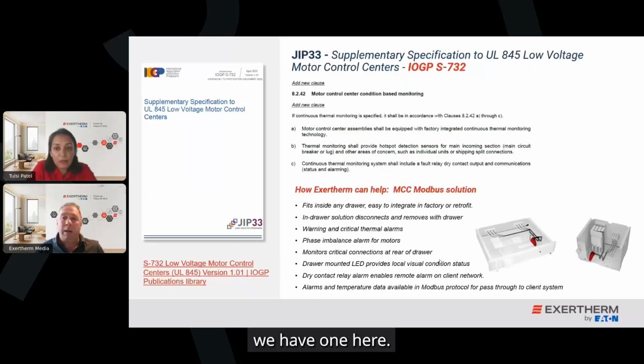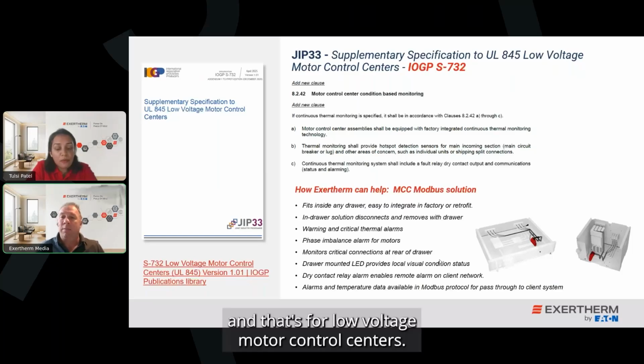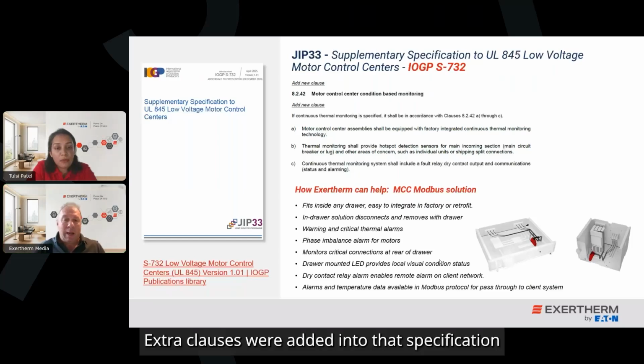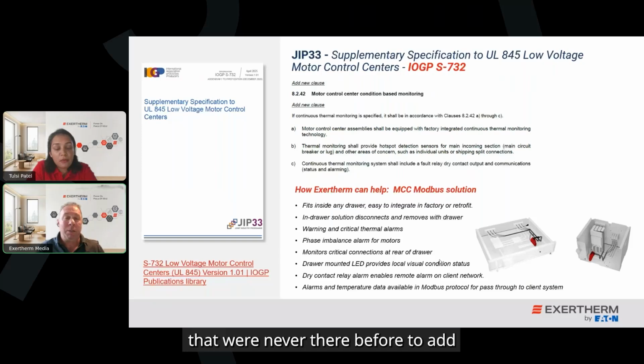We have one here, IOGP S732, as its number is, and that's for low voltage motor control centers. Extra clauses were added into that specification that were never there before to add continuous thermal monitoring.